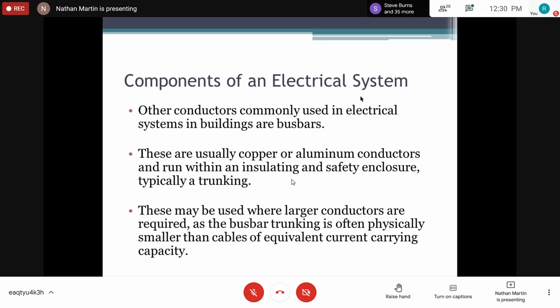There are several applications. In an industrial setting, you'd have a bus bar chamber, and then all the different sub-circuits are connected to that bus bar chamber through a breaker, right? So we're talking about large utility rooms, built from metal enclosures. A lot of these bus bar chambers are built to specification. Compare that to your small commercial or residential setup, where you have one meter box and one distribution panel in most houses, where you connect from that meter box to your panel box and then from your panel box to the different sub-circuits.